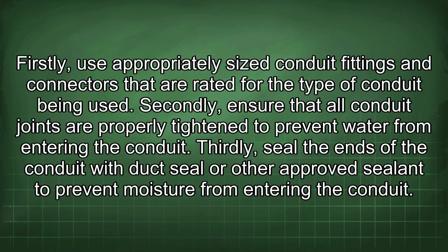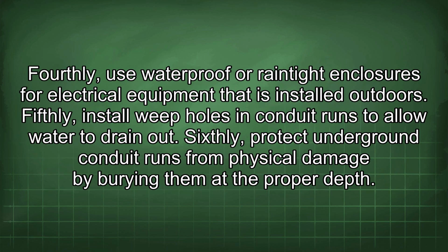Firstly, use appropriately sized conduit fittings and connectors that are rated for the type of conduit being used. Secondly, ensure that all conduit joints are properly tightened to prevent water from entering the conduit. Thirdly, seal the ends of the conduit with duct seal or other approved sealant to prevent moisture from entering the conduit. Fourthly, use waterproof or rain-tight enclosures for electrical equipment that is installed outdoors.